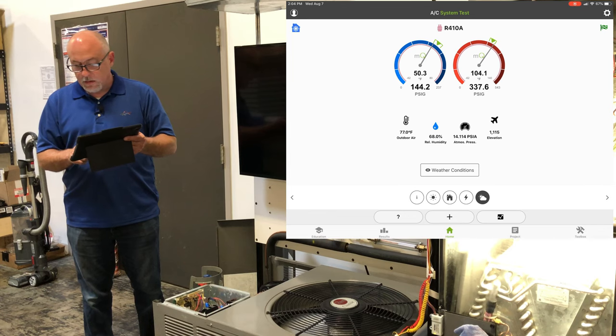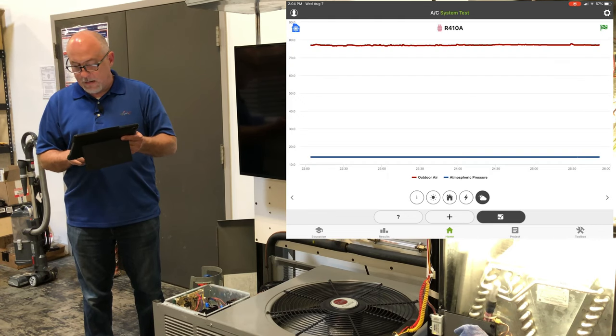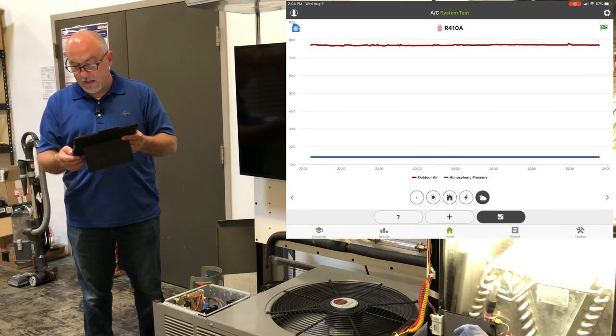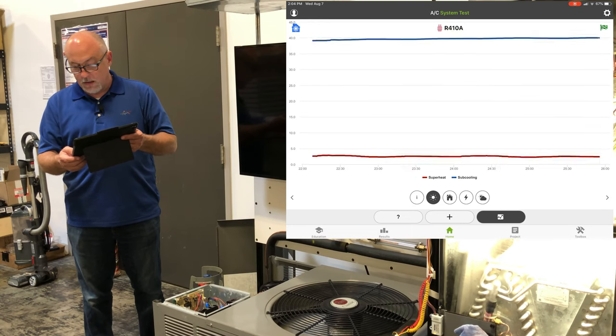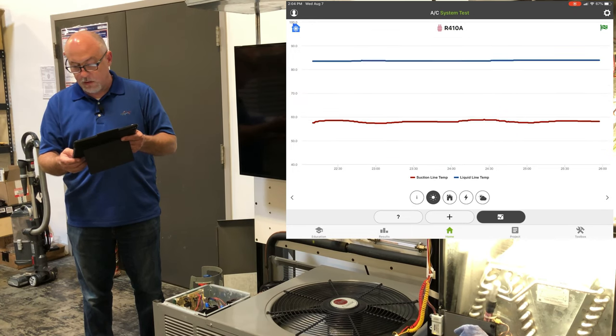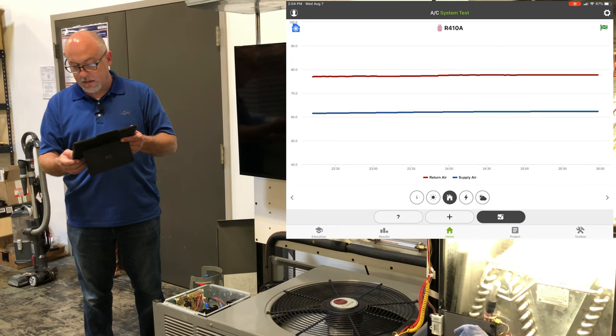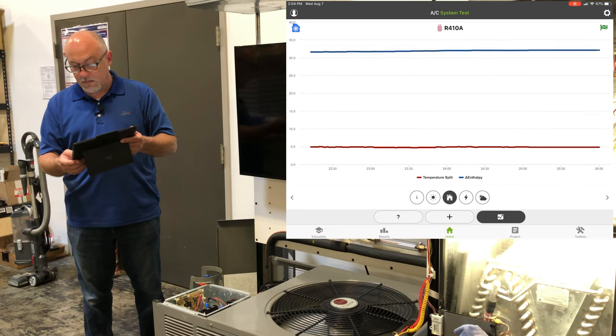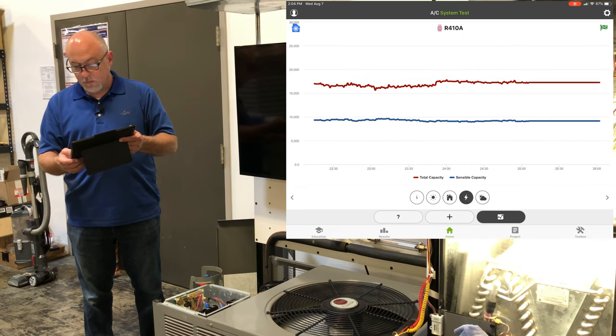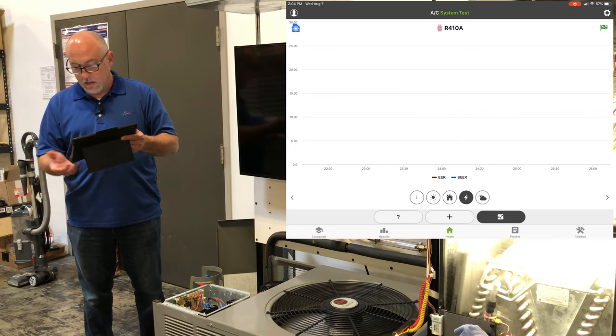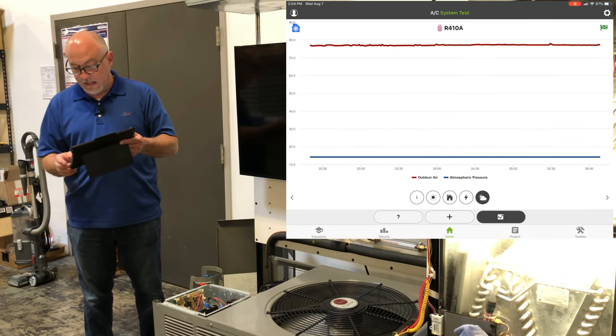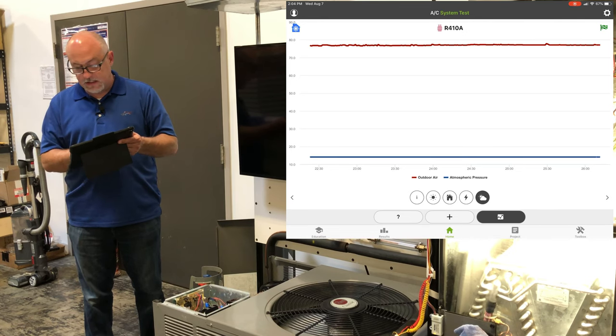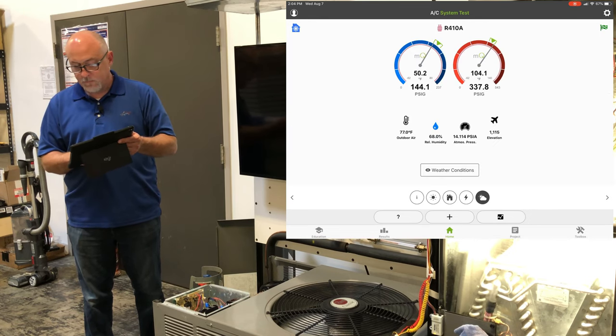Now down at the bottom, there's another sub menu down below that. If you tap on that you'll see that that's our trending bar. We can scroll through there and look at low and high pressures, superheat and sub-cooling, suction line temp, liquid line temp, return air, supply air, temperature split, total capacity and sensible capacity, and then back to the EER. There's no EER because we don't have electrical data, but that is the trending menu and allows us to see several minutes of data and how it's trending.